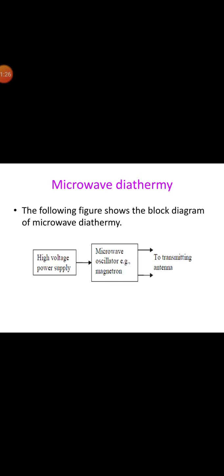The technique of application of microwave diathermy is very simple. Unlike shortwave diathermy, where the patient is brought in as a part of the circuit, the microwaves are transmitted from an emitter and are directed towards the portion of the body to be treated. Thus, no tuning is necessary for individual treatments. These waves pass through the intervening airspace and are absorbed by the surface of the body, producing the heating effect. And now let us see how the microwaves are produced.